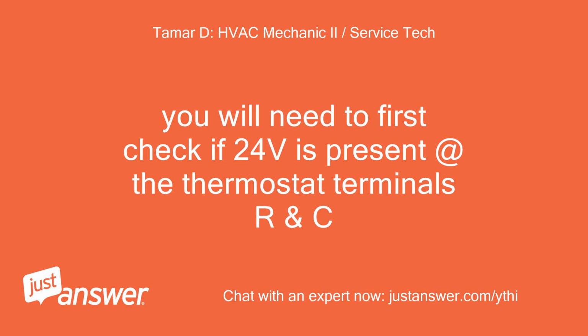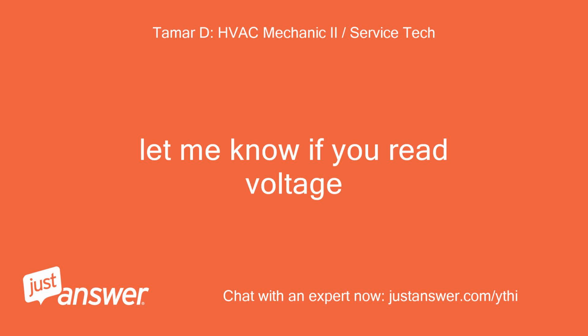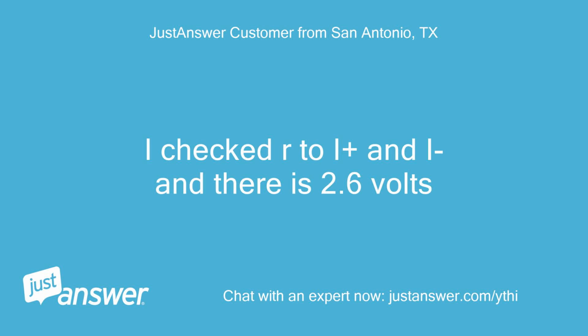You will need to first check if 24 volts is present at the thermostat terminals R and C. I have an SLP98V Lennox furnace. Let me know if you read voltage. No voltage R to C with door switch held closed. I checked R to I plus and I, and there is 2.6 volts.